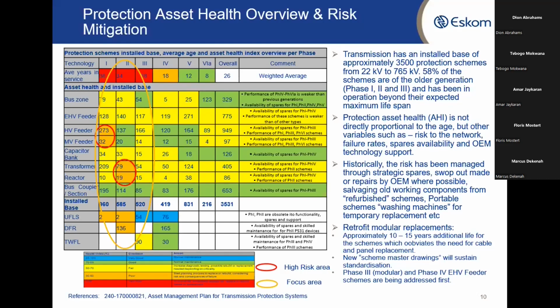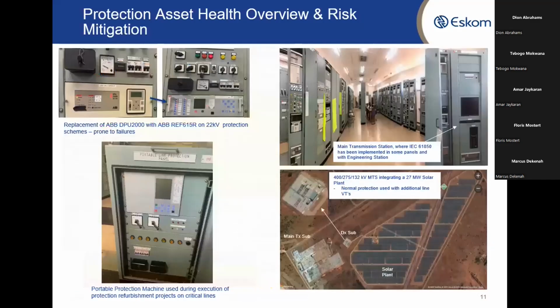So we are putting projects to make sure that we extend the life of some of these assets, and we also issue protection projects for that. Just to demonstrate some of the work that has been done, as you can see on the top picture, you have replaced the ABB DPU that was frequently failing on the MV feeders, where mostly are radial lines, replaced with the ABB REF feeder.